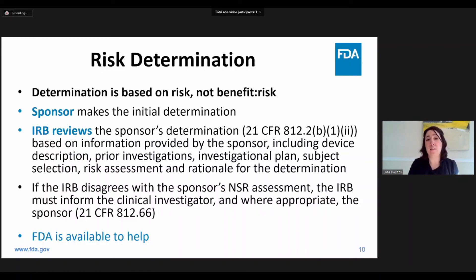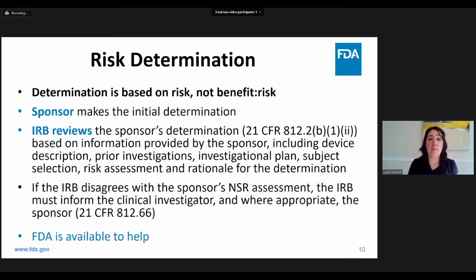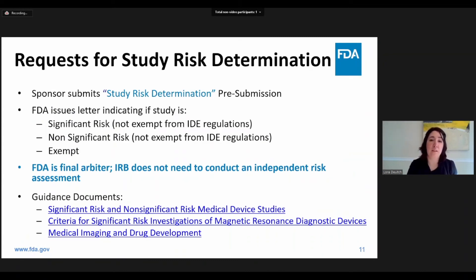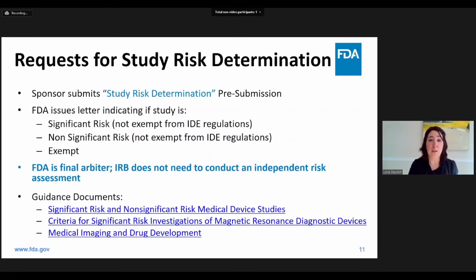If you decide that your study is non-significant risk, you would probably want to approach the IRB first, since a non-significant risk study would not need FDA oversight. However, if the IRB decides that your study should be classified as significant risk, then you will need to submit your application to the FDA for approval before the study can begin. FDA can be contacted to help with study risk determination using our Q submission process. A sponsor can submit their planned study for a study risk determination, and the result is a formal determination made by the FDA — an official letter indicating if the study is significant risk, non-significant risk, or exempt from IDE regulations. If a sponsor receives a study risk determination decision from the FDA, that decision is final. The FDA is the final arbiter, and the IRB does not need to do an independent risk assessment.